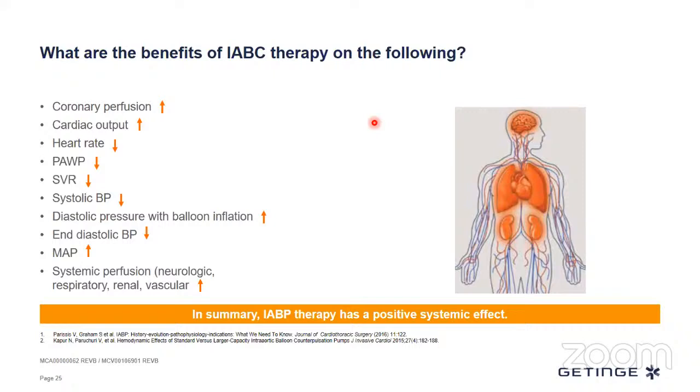If the heart muscle is so deteriorated that there's not much cardiac output, then there's a need to escalate therapy. You start with the balloon pump and you escalate therapy further. If the heart muscle is not working, the balloon pump is not going to work. We work with the patient's existing cardiac output. And these parameters you are quite familiar with.